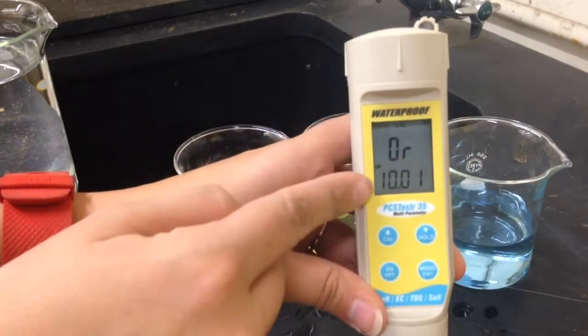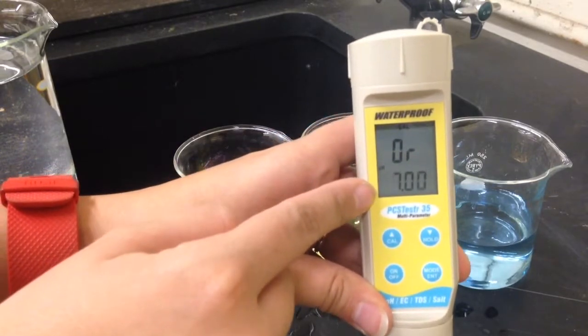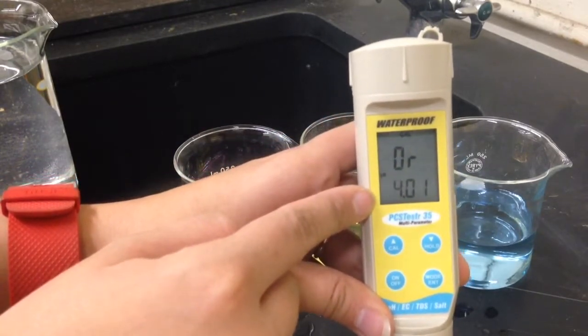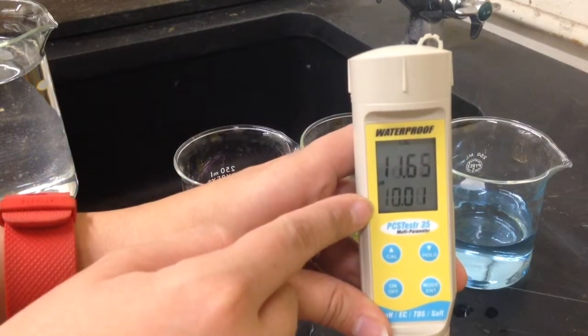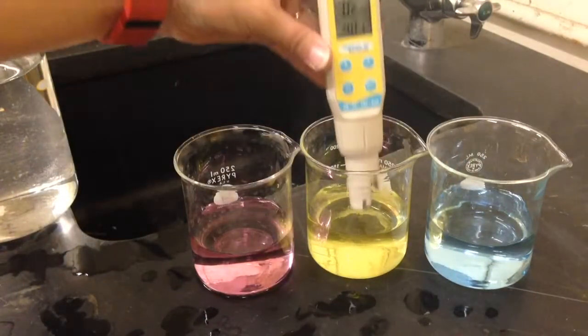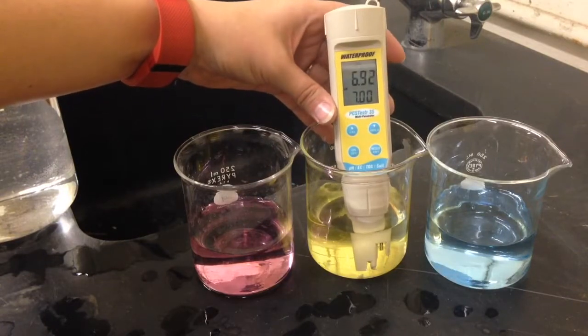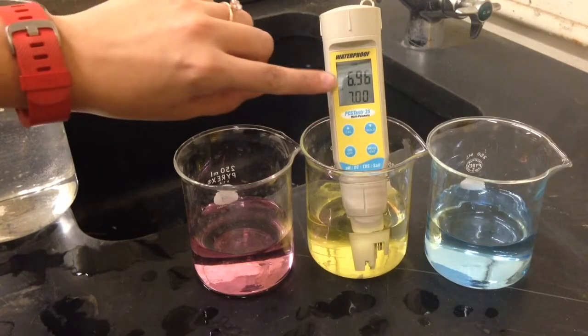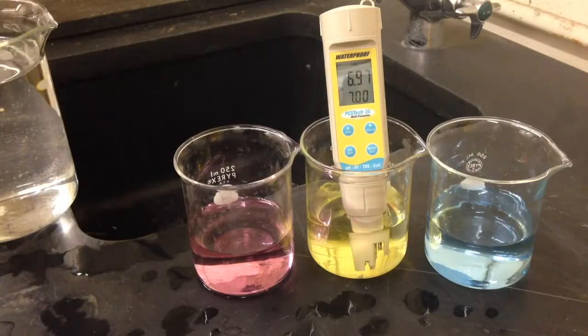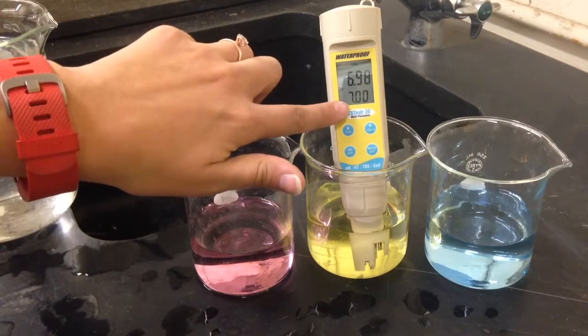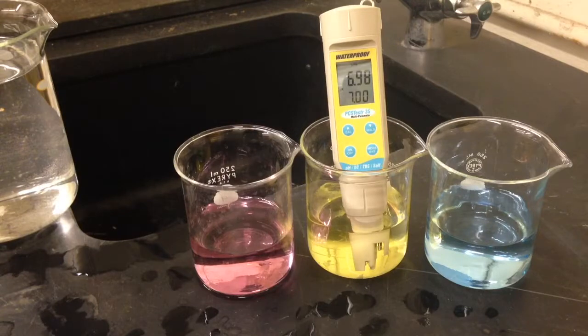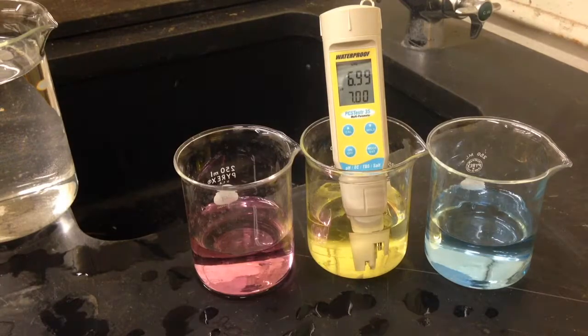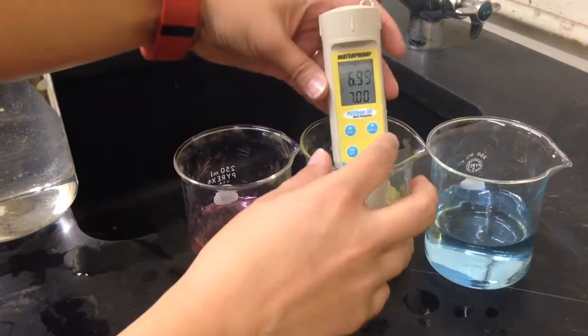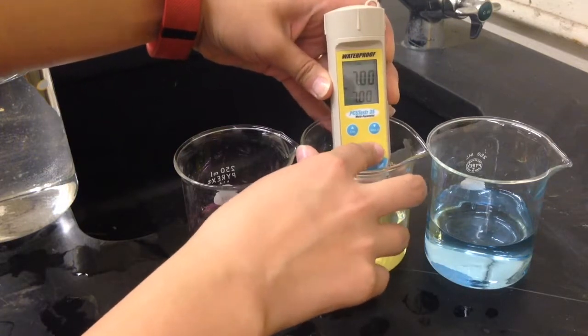You can see that this bottom display, or the secondary display, is flashing the pH values of each of the pH standard solutions. We're going to begin by immersing our meter in the neutral solution with the pH of 7. The primary display reads the actual pH value of the container, and the secondary display will show the closest pH standard. When the meter is immersed, we must wait for the primary display to stabilize. Once the primary display has stabilized, we will push the Mode Enter button.